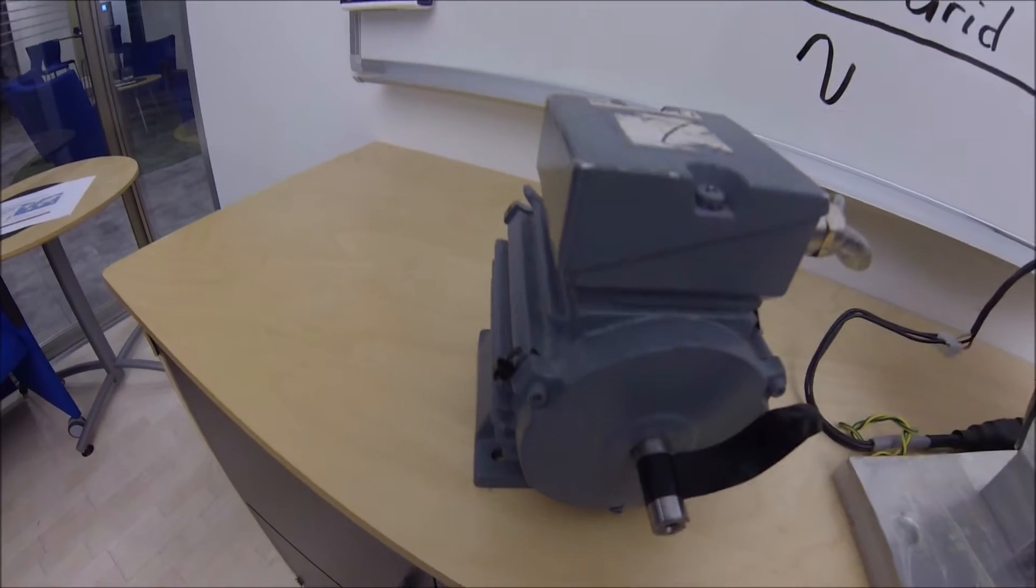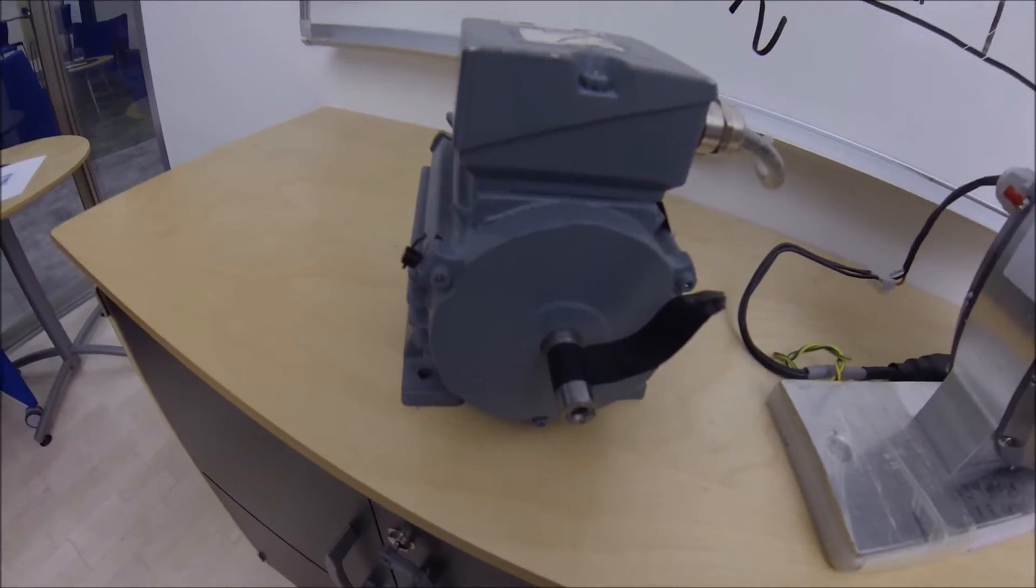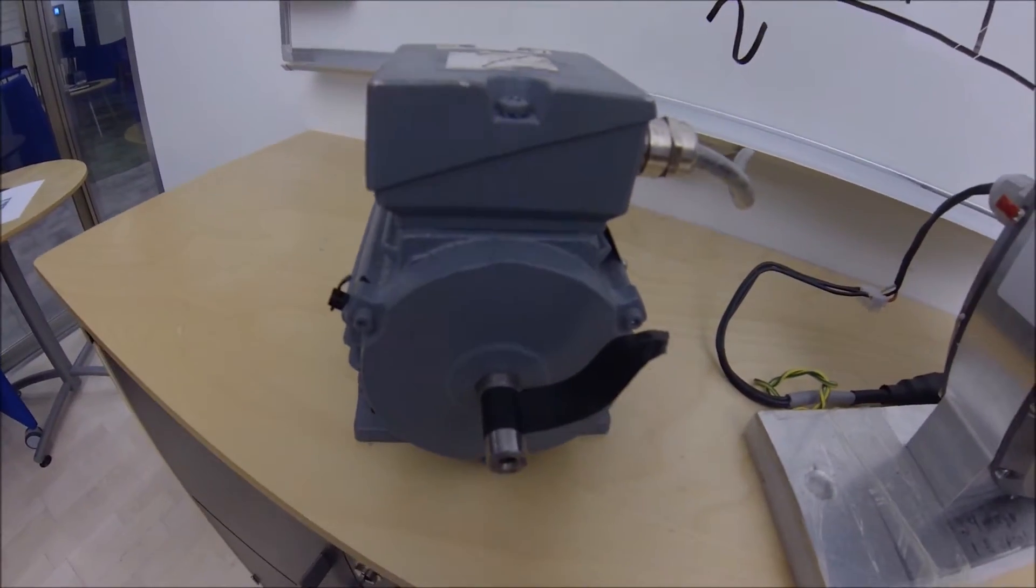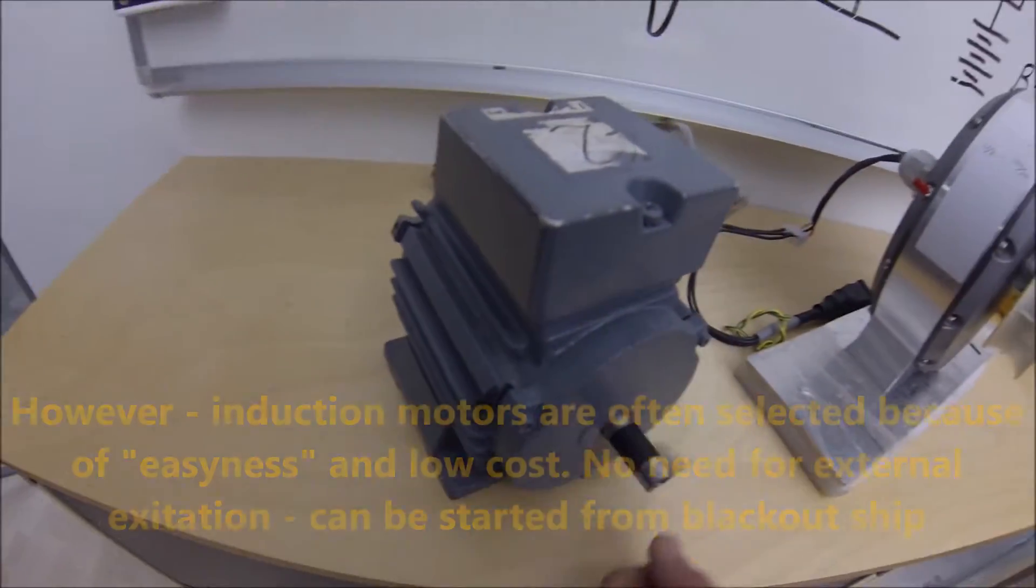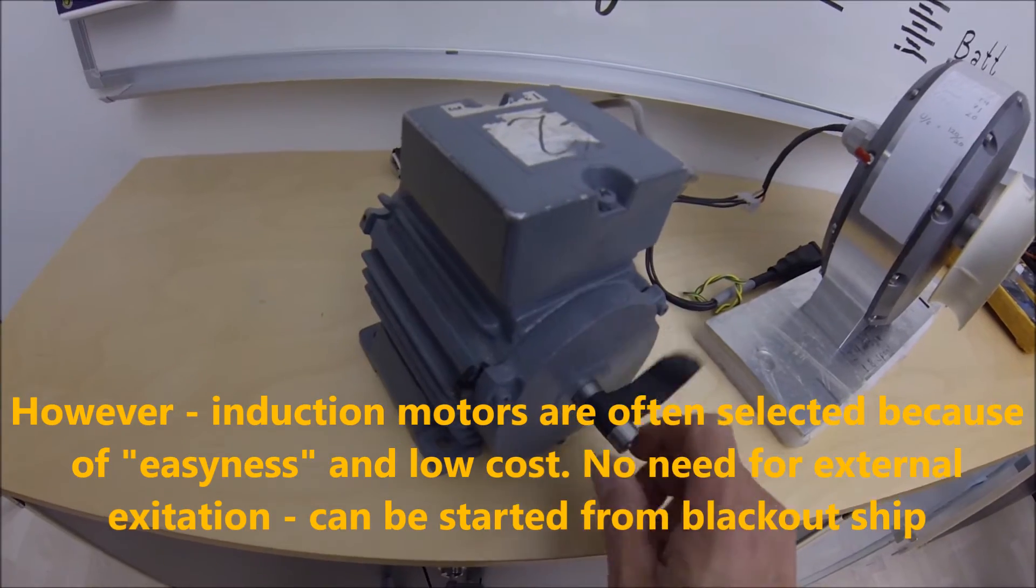The current running here, a reactive current of about 40 percent of the motor nominal, causes higher losses. So induction motors are not the highest efficiency for generator use.